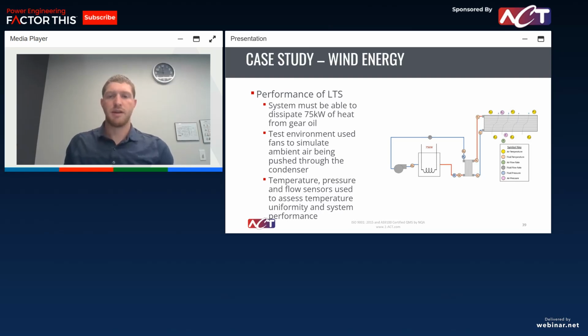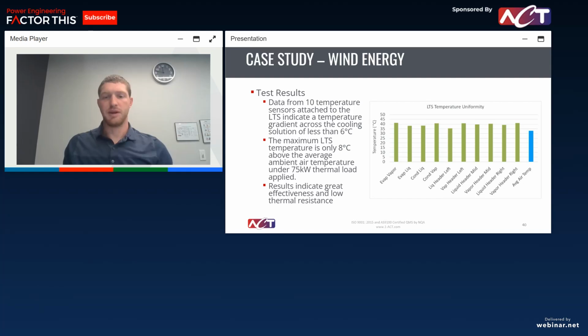Here's some of the testing we did when this was first implemented. Since then we've implemented, I want to say thousands, but at least hundreds of these on wind turbines. We were looking at dissipating 75 kilowatts of heat from that gear oil. We simulated ambient air going across that coil, and we were testing the pressures and temperatures at 10 different locations along the loop. What we were really looking for was temperature uniformity and a low temperature delta. What we saw was just a 6-degree gradient across the entire loop, so pretty good isothermality through the system, and then only an 8-degree temperature difference from the ambient air to that max temperature.